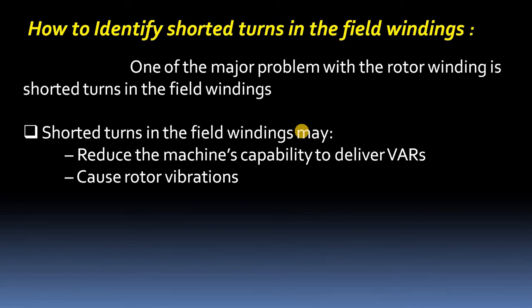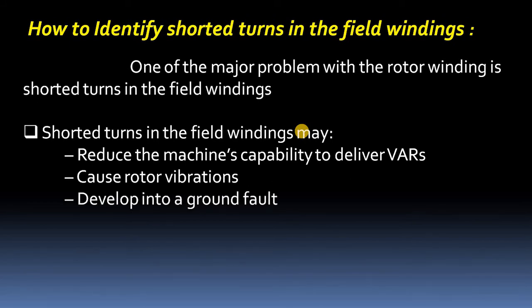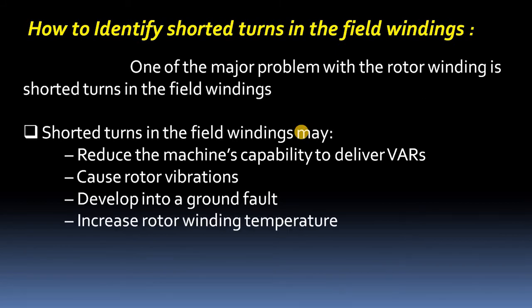Whenever shorted turns are present there is an unbalance in the air gap flux density, and that unbalanced air gap flux generates rotor vibrations. Additionally, shorted turns in the field winding can develop into a ground fault.